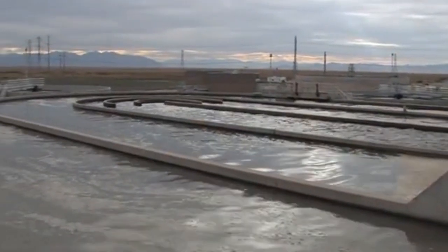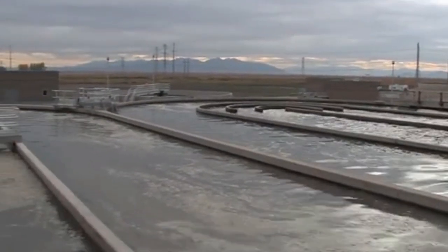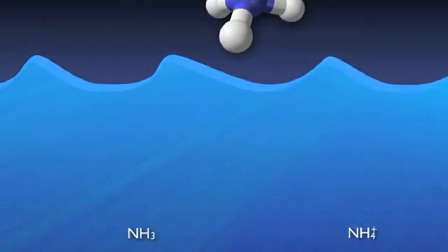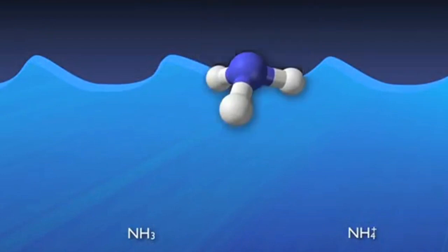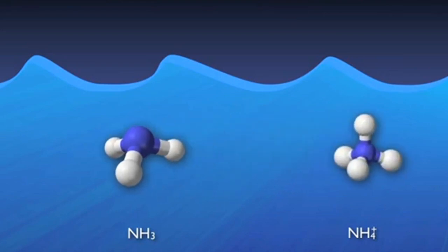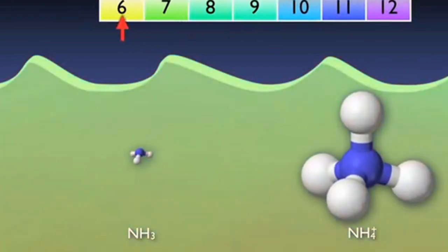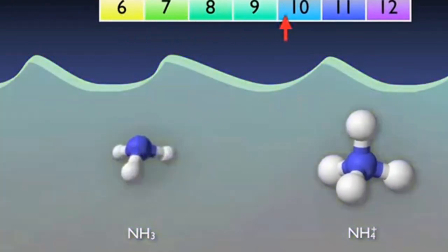Let's go back to the beginning and take a closer look at each of these important steps in the nitrogen removal process. First, as a natural reaction in an aqueous solution, the vast majority of the organic nitrogen immediately hydrolyzes into ammonia. Most of this ammonia automatically converts to the ionic form, ammonium. The equilibrium between the gaseous and ionic forms of ammonia is heavily impacted by the pH of the water. A more acidic solution will favor the ionic form, ammonium; a more basic will favor the gaseous form, ammonia.